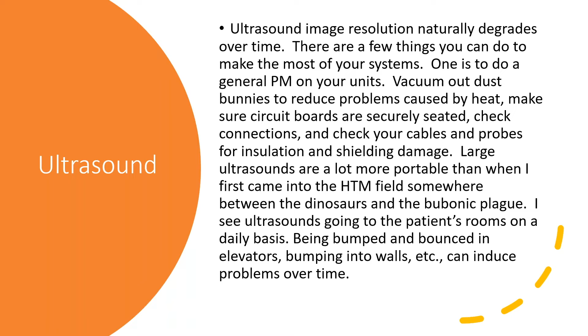Okay, next place to look, ultrasound probes. Has the soft scanning surface of the probe been damaged? Any break in the physical continuity of the probe surface will induce image artifact. Ultrasound crystals will degrade over time, and I've got a very specific case study coming up on this very thing. You can QC your probes, check for image continuity, look for dropout in your image field, especially when you're moving your probe over the phantom. Make sure the picture stays there as you move. Watch for what moves and what does not in the image field as you move your probe. Getting ultrasound probes repaired is relatively inexpensive compared to the improvement that you will get. There are numerous independent companies servicing imaging and specifically ultrasound probes.